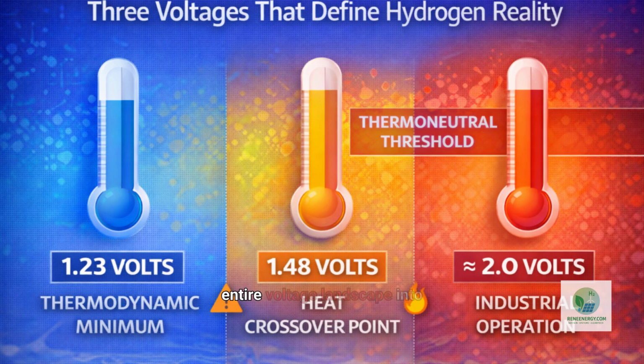Image 3 simplifies the entire voltage landscape into one visual truth. There are 3 voltages that define hydrogen reality. Around 1.23 volts marks the thermodynamic minimum. Around 1.48 volts marks the heat balance threshold. Around 2.0 volts marks industrial operation. The shaded region above 1.48 volts is where cooling systems are mandatory. That shaded region is infrastructure. It is not optional. When someone quotes 1.23 volts without referencing the other 2 voltages, they are describing chemistry, not engineering.